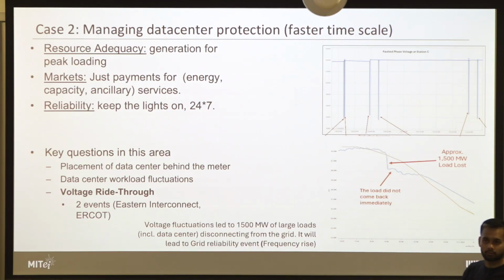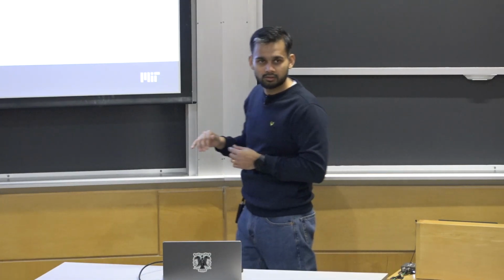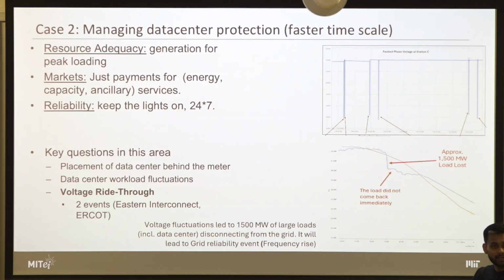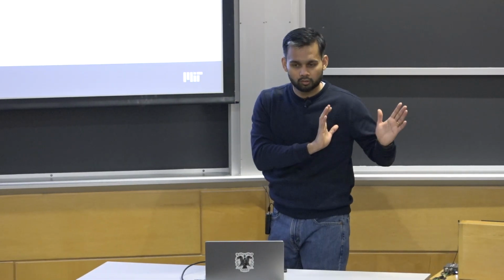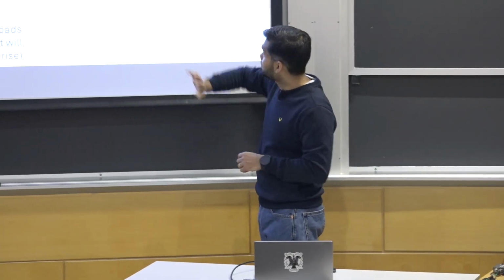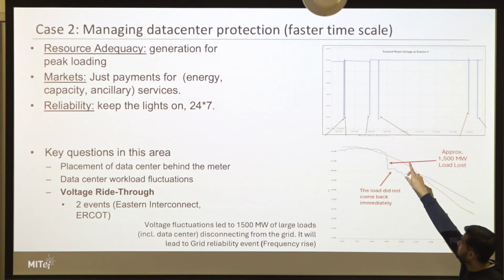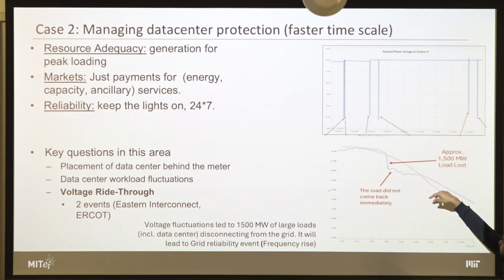There was a transmission line fault which led to some weird voltage signatures. Not that bad, because the rest of the grid and the rest of the loads stayed connected. But data centers, because their protection is over-engineered, saw 3 of those voltage pings, and they disconnected.